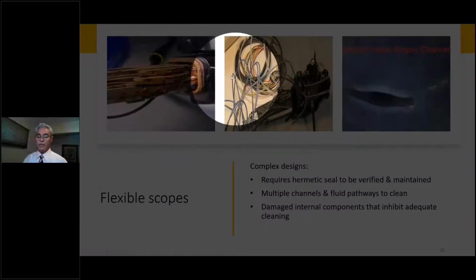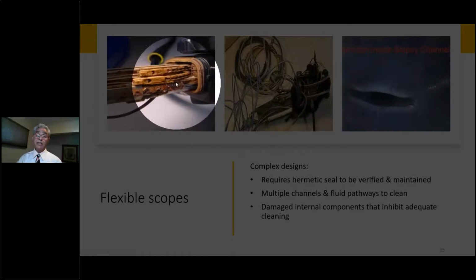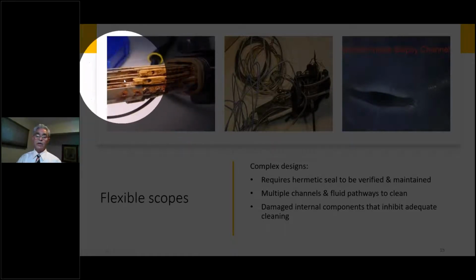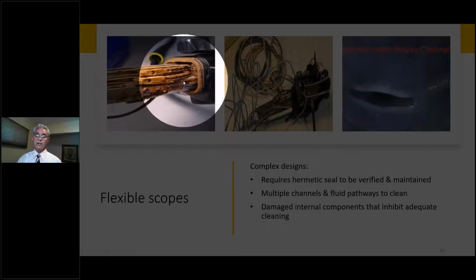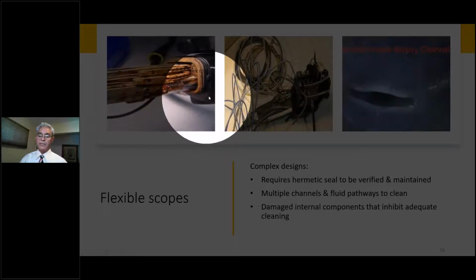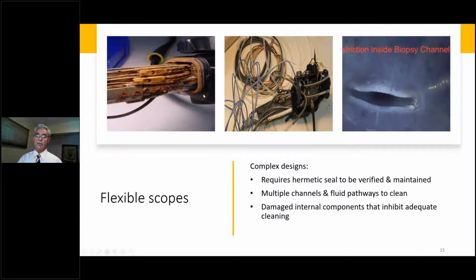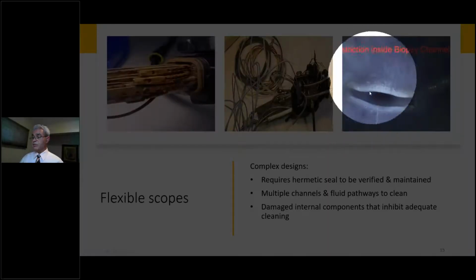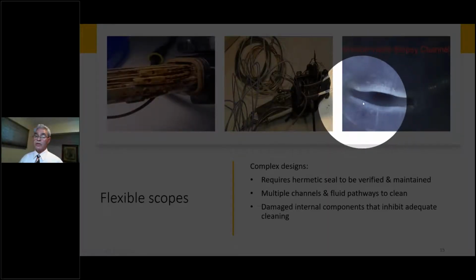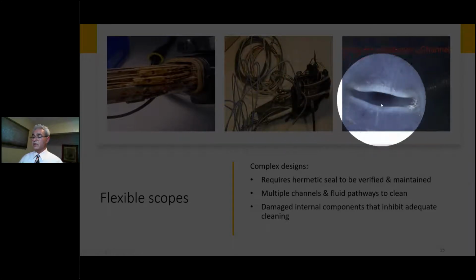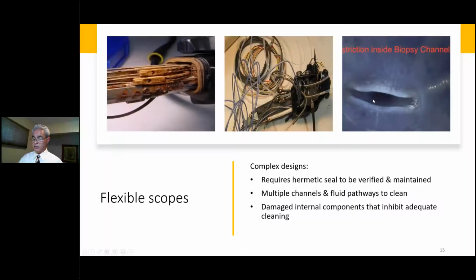This is due to fluid invasion—for example, maybe there was a leak inside the endoscope and over time fluid got in. Again, we'll tell you what's going on, why the leak got inside the scope. Here, for example, is damage you can see without having to destroy the scope, just by looking with a flexible inspection scope, and you'll see there's damage inside.